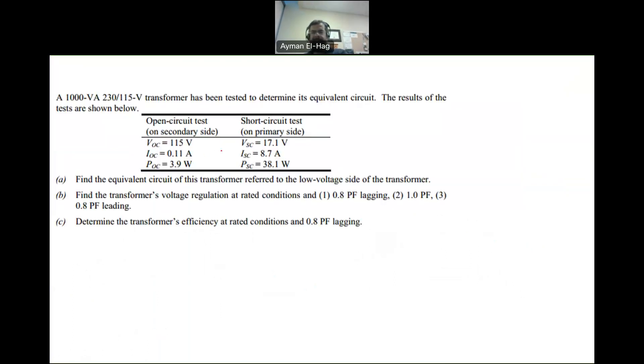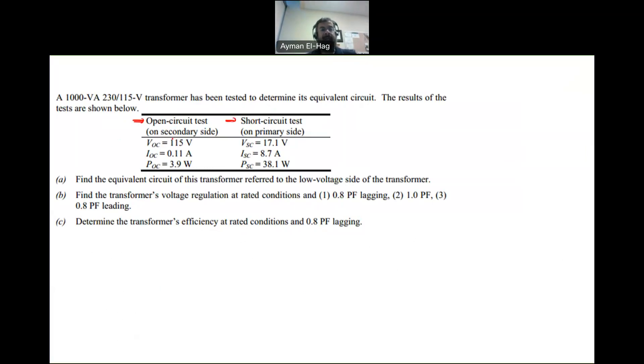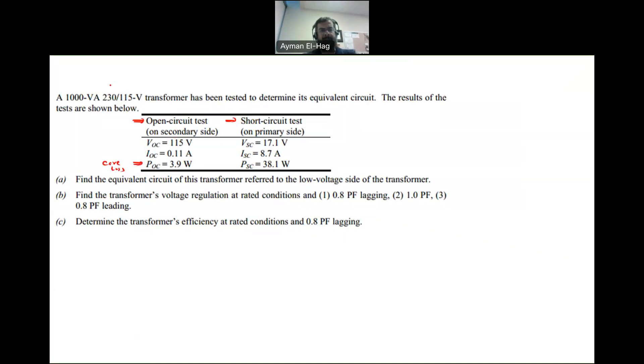We have a 1000 VA, 230 by 115 volt transformer that is tested to find the equivalent circuit. The open circuit test was done at the secondary side or the low voltage side, where we apply the rated voltage of 115 volts and measure the open circuit current and the open circuit power, which is the core loss. The short circuit test was done at the primary side or the high voltage side, where we apply a small voltage to have the rated current flowing in the windings and measure the copper loss.